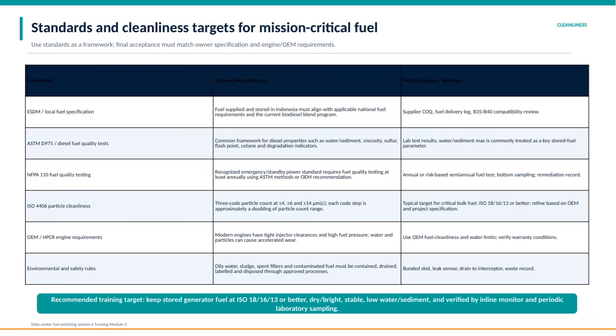Next, ASTM D975 provides standardized tests for diesel fuel, measuring properties like water and sediment levels, viscosity, sulfur content, flash point, cetane number, and degradation indicators. Among these, water and sediment content is often the most emphasized parameter because excess amounts compromise fuel stability and performance. We rely on lab test results to verify these criteria. NFPA 110 sets standards for emergency and standby power fuel quality, requiring at least annual testing using ASTM methods or as recommended by the engine OEM. This includes bottom sampling to check for contaminants, with records maintained for any corrective actions taken.